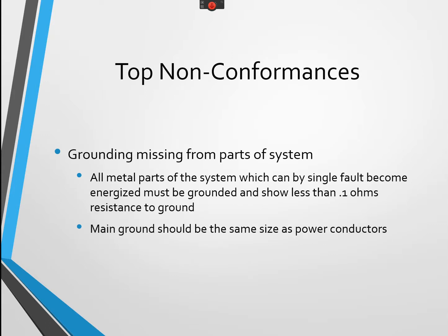Grounding is missing. We talked about that. You don't have to ground every single panel in your machine. That's overkill. Lots of people do it, and I'm okay with that. But really, we're looking for the enclosure covers and other parts that might become energized in a fault. And that main ground coming into your machine doesn't have to be, but it's best practice to have that main ground be the same size as all the power conductors.